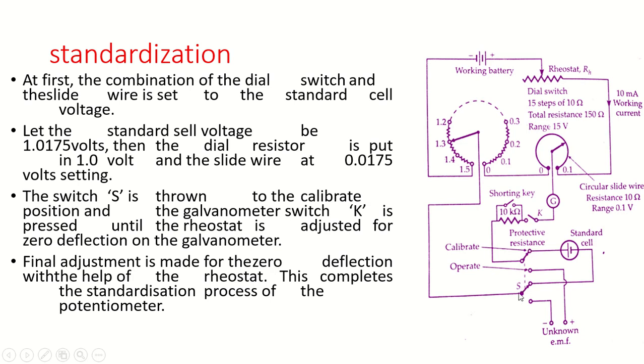Next, put the switch in calibrate position and close the key. Check whether the galvanometer shows zero deflection. If it is not showing zero deflection, adjust the rheostat or the protective resistance to achieve zero deflection. Once the galvanometer shows zero deflection, the standardization process is complete — meaning the standard cell EMF of 1.0175 volt matches the voltage indicated by the dial settings, confirming the potentiometer is calibrated.